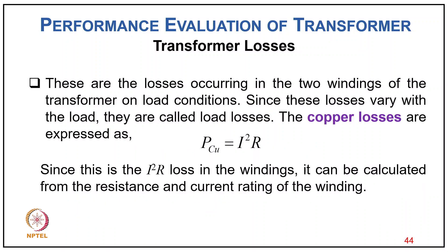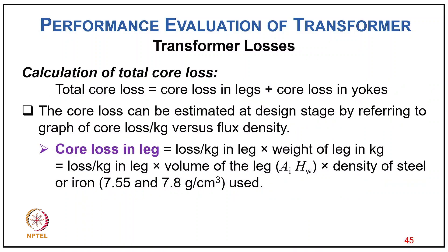Copper losses occurring in the two windings under load conditions vary with load and are called load losses, expressed as PCU = I²R. Calculation of total core loss = core loss in leg + core loss in yoke, estimated at design stage from a graph of core loss per kg versus flux density. Core loss in leg = loss per kg × volume of leg × density of the steel used.